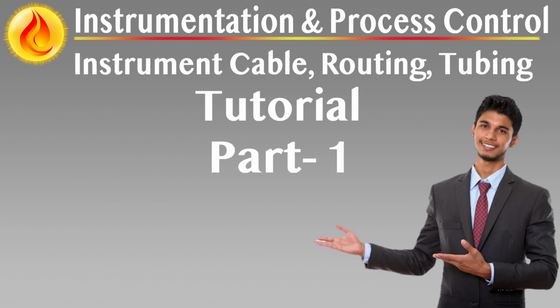Cabling exposed to potential physical or chemical hazards must incorporate steel wire braiding, SWB, or steel wire armoring, SWA. Additional chemical or moisture barriers are necessary if HDPE sheathing is not included.